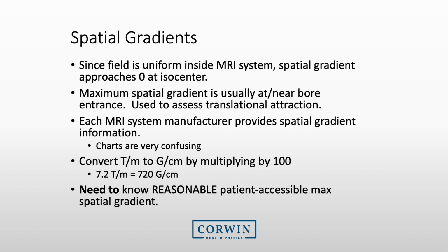A confusing item on these conditional statements is the spatial gradient. Let me take a few moments to explain this concept. The spatial gradient is the change in magnetic field over distance and is usually given in Tesla per meter or Gauss per centimeter. Since the magnetic field within the magnet is uniform, the spatial gradient inside the bore is usually low or near zero. The largest spatial gradient is typically outside the magnet at the bore entrance.